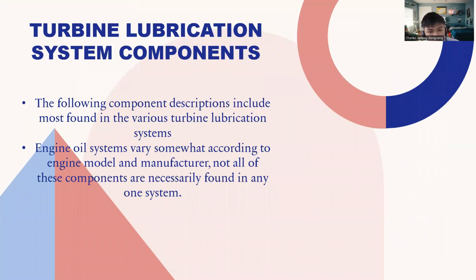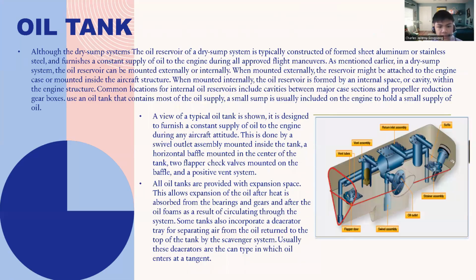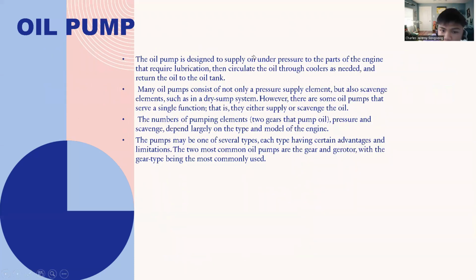So let's go back and check if you all still remember the components of a turbine lubrication system. First is the oil tank. We use oil tanks so that... first is the oil tank, which has a dry sump and wet sump. Next is the oil pump. We use the oil pump to supply oil under pressure to the parts of the engine that require lubrication, then circulate the oil through coolers as needed, and return the oil to the oil tank.